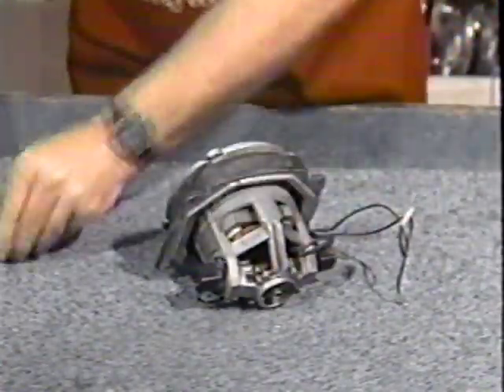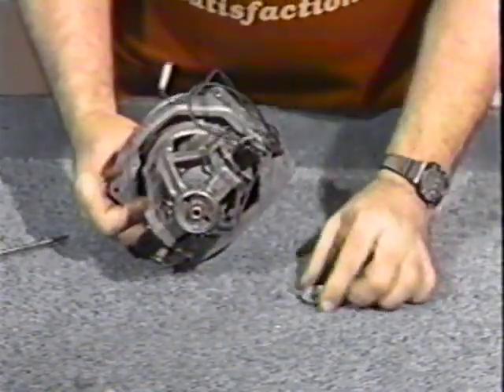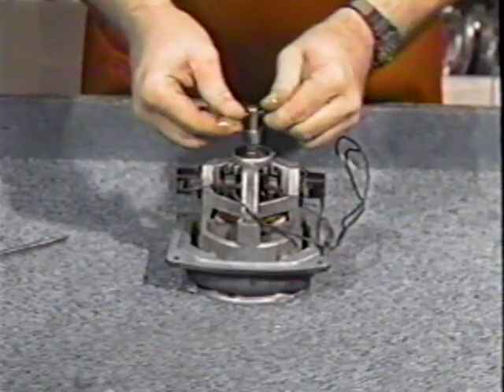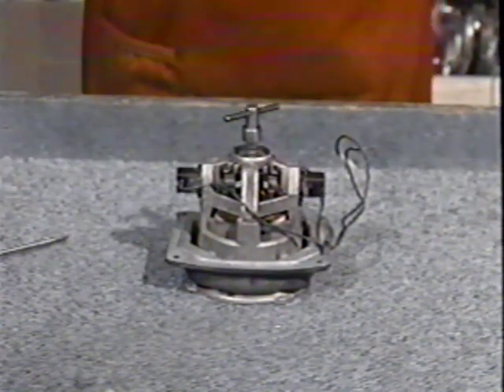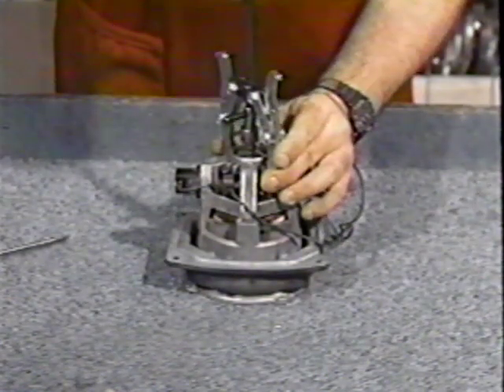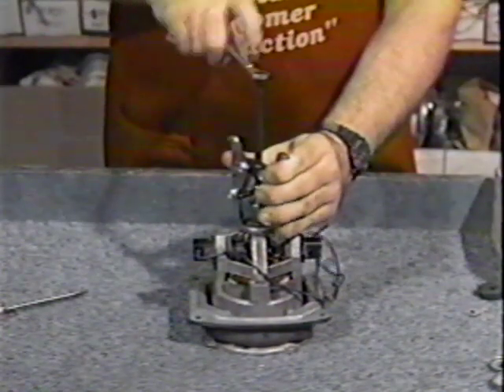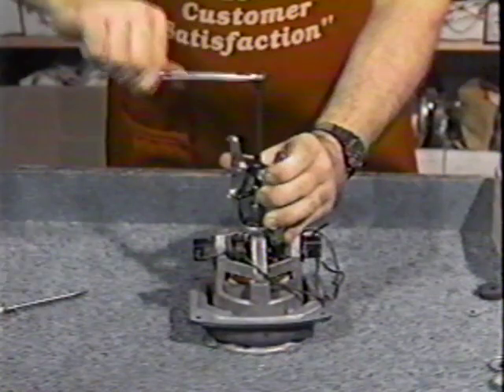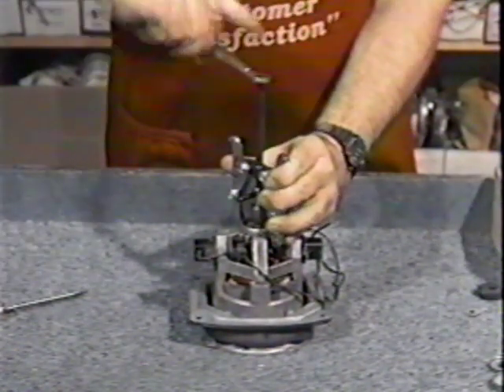Now remove the bottom cap and spacer and place aside. To insert the new bushing, place it on top of the existing one and assemble the gear puller into position. Rotate the screw to press the new bushing in. When the arbor bottoms out, the new bushing is correctly located.